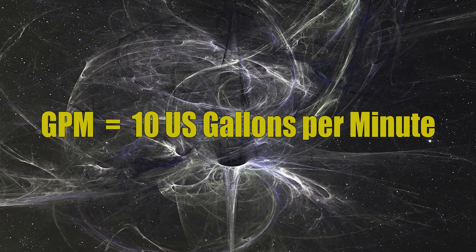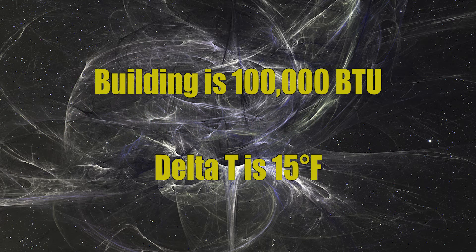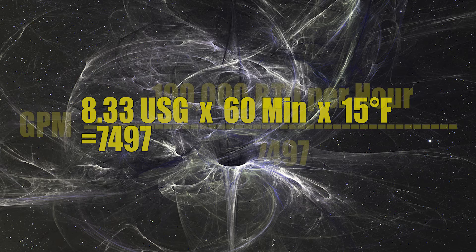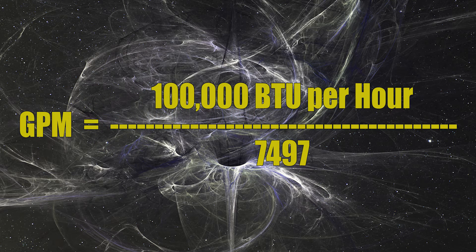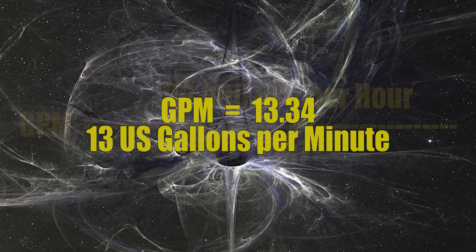But say I don't want to use a delta T of 20 — say I want to use a more common one like a delta T of 15 degrees Fahrenheit. I'll do the same math: 8.33 times 60 times 15 equals 7,497. Then I take my BTU load of 100,000 divided by 7,497, and that equals 13.34 GPM — you can safely round that off to 13.